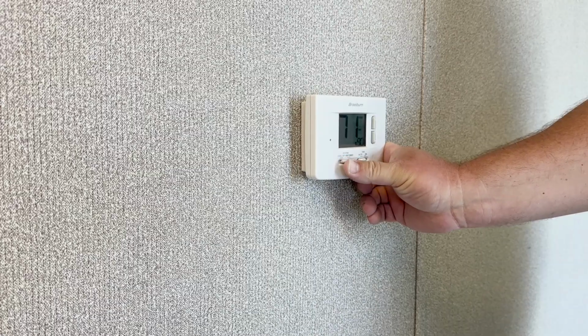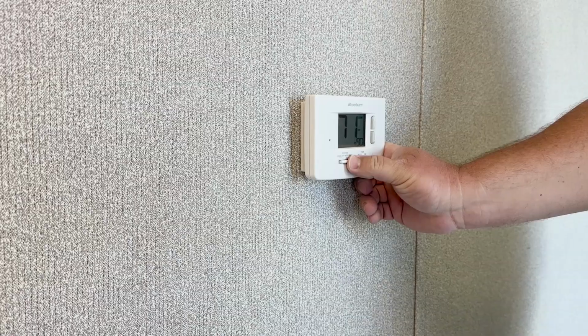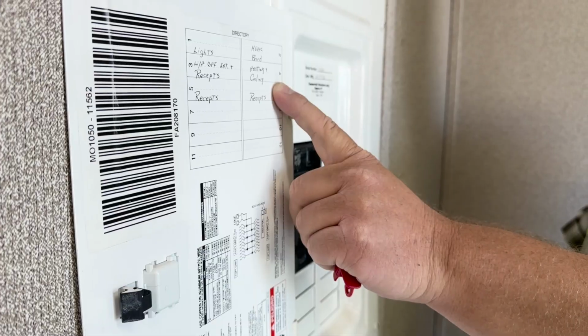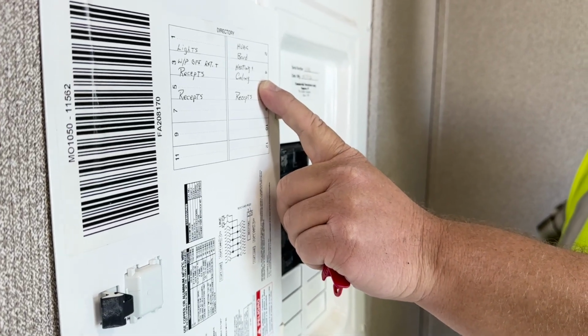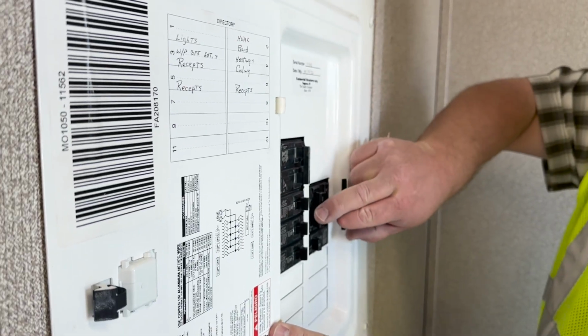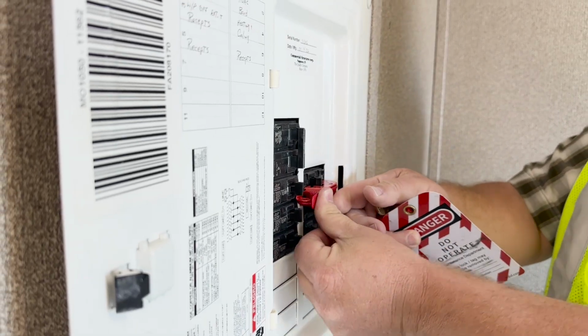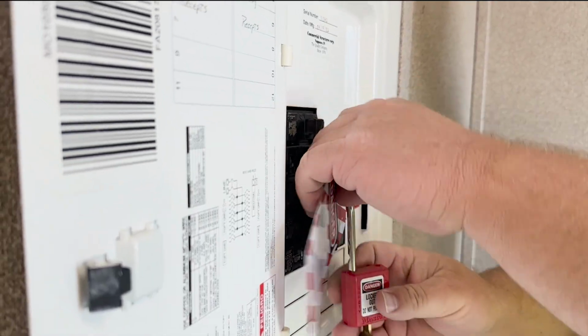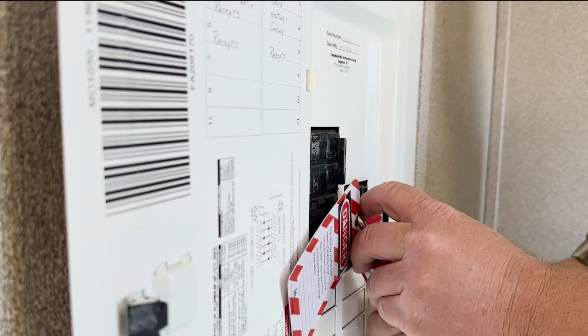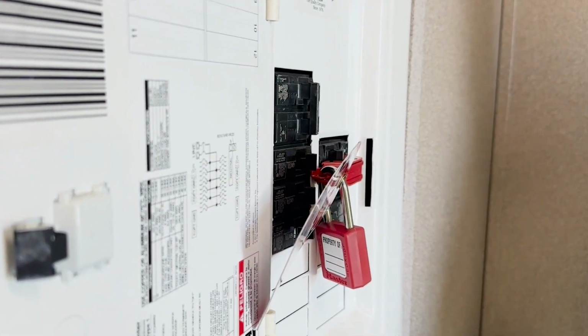To start, always turn off the AC unit using the thermostat inside the mobile office. Then turn off the power to the HVAC unit. This can be completed either on the internal main electrical panel or the panel on the side of the HVAC system. Then, apply the lock and tag to the electrical panel that you switched off.